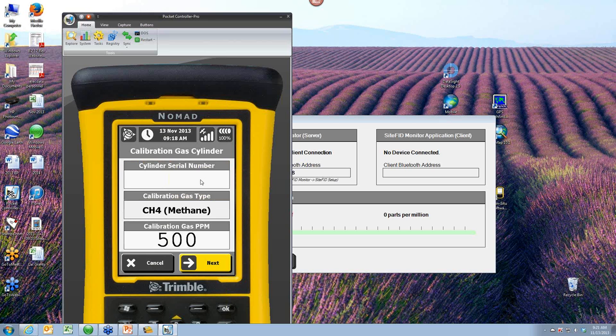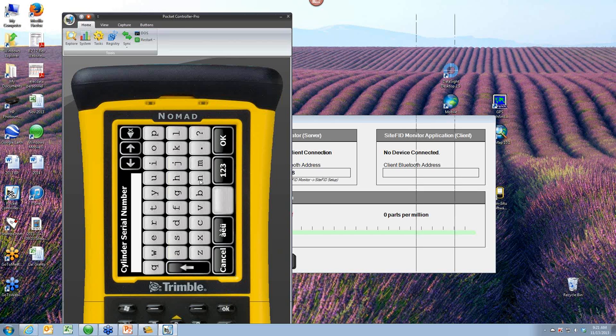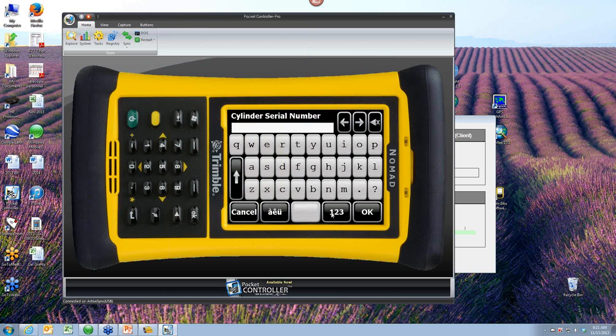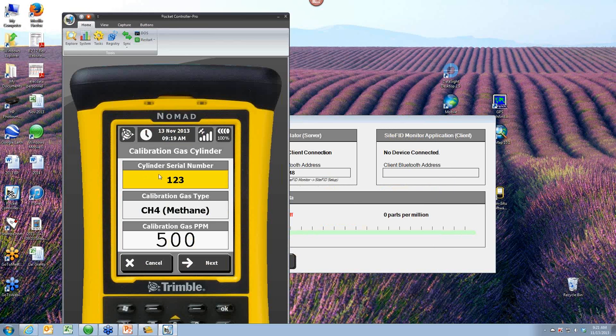Now remember, keep in mind for regulatory reasons, the first thing it's asking me is, hey, the cylinder that you're using to calibrate your methane, what's that cylinder number? So I can go in there, and just for this particular demonstration I'll just put 1, 2, 3. But obviously, those things are 12, 13, 14 numerals and letters long. So there, I've got that in there. There's my calibration gas. I'm using 500 ppm. And again, it's very simple.